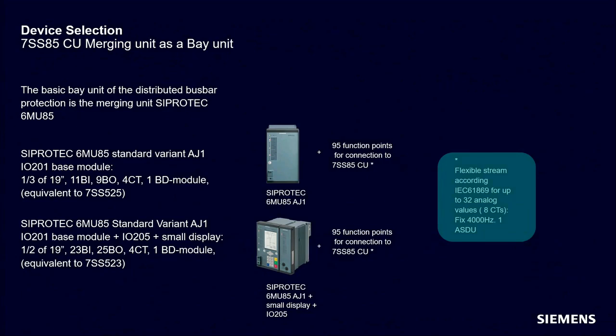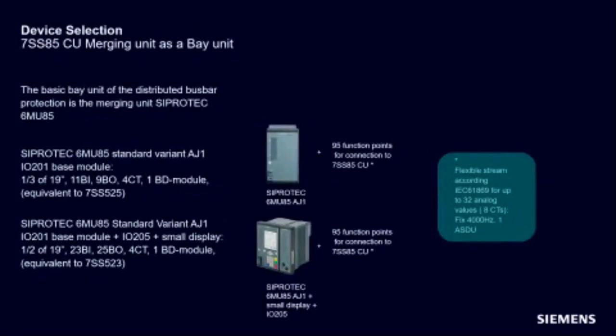One additional remark: 95 additional function points you have to buy. With these 95 additional function points, you buy a flexible stream according to IEC 61869, and this stream is suitable for up to 32 analog values, which means this is possible for up to 8 CTs. In contrast to the bay unit of the 7SS52, where it was only possible to cover one CT each time, with the 6MU85, or also with all other modular SIPROTEC 5 devices, you can cover up to 8 CTs, 8 current measuring points, within one bay unit.